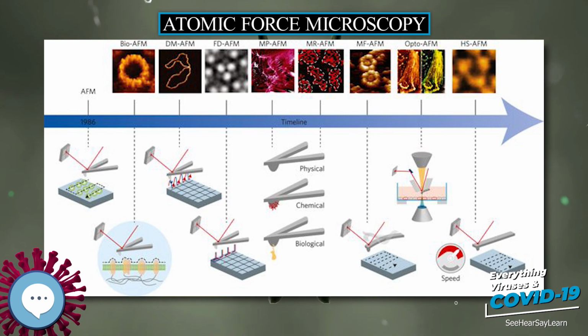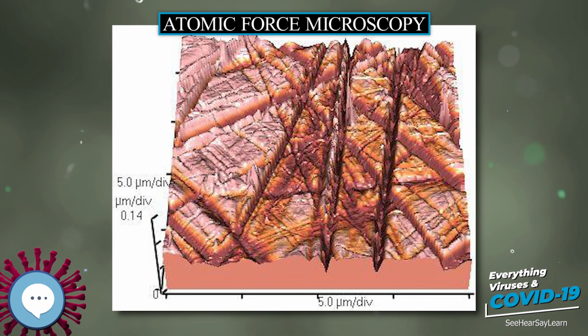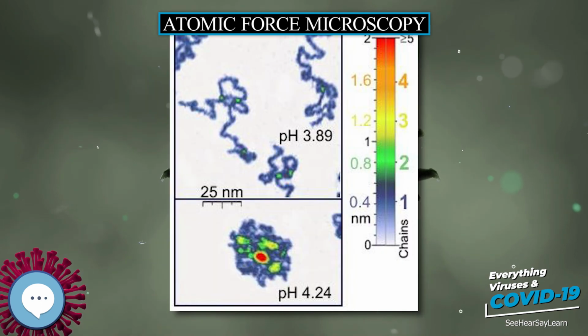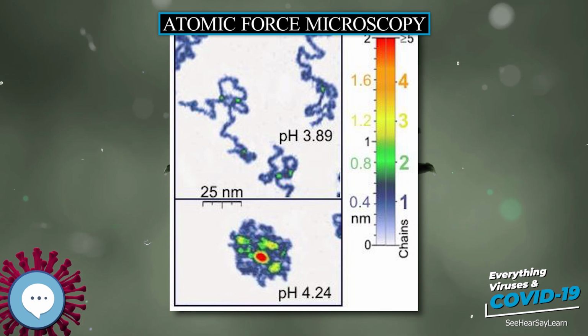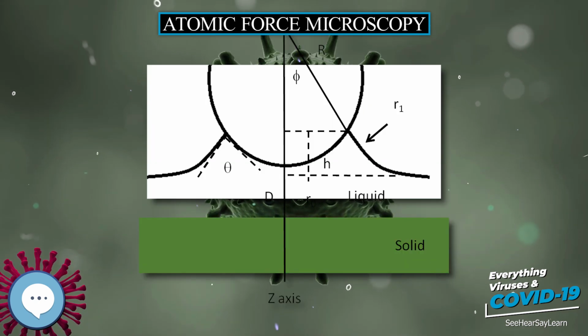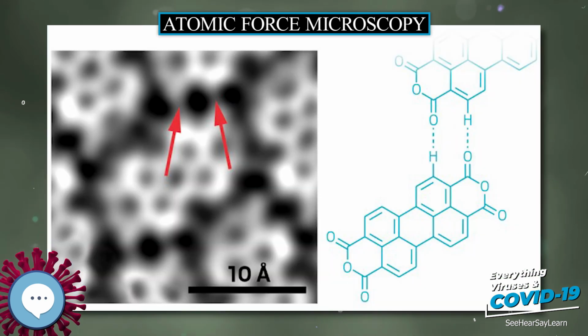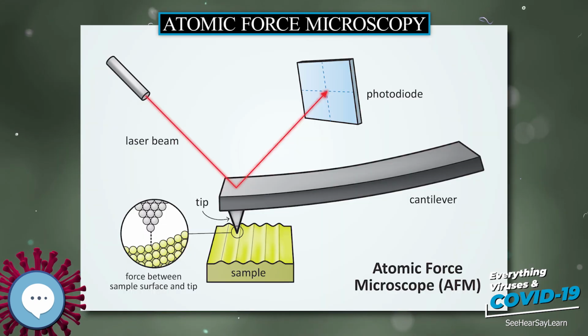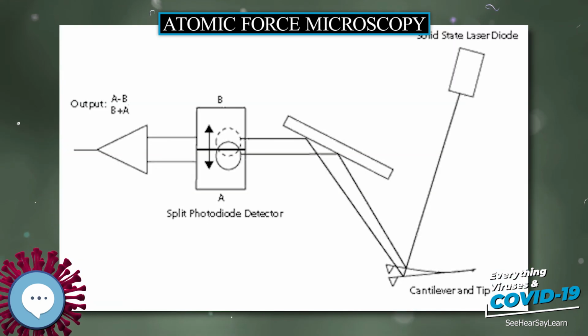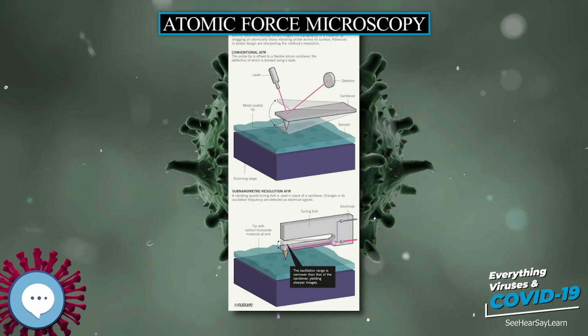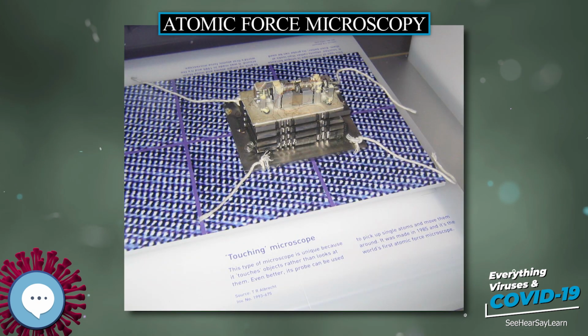Just the tip is brought very close to the surface of the object under investigation. The cantilever is deflected by the interaction between the tip and the surface, which is what the AFM is designed to measure. A spatial map of the interaction can be made by measuring the deflection at many points on a 2D surface. Several types of interaction can be detected. Depending on the interaction under investigation, the surface of the tip of the AFM probe needs to be modified with a coating. Among the coatings used are gold, for covalent bonding of biological molecules and the detection of their interaction with the surface, diamond for increased wear resistance, and magnetic coatings for detecting the magnetic properties of the investigated surface.